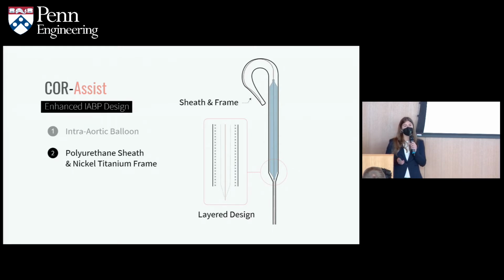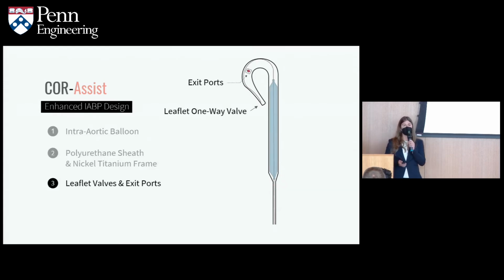The polyurethane sheath reaches into the left ventricle, providing direct support to the ventricle and therefore increasing the flow rate. The nickel titanium frame provides structure for a device and allows for it to expand once pushed out of a catheter due to its memory properties. In order to allow for proper flow in and out of the left ventricle, we included a leaflet one-way valve and exit ports. The one-way valve allows for blood to be pulled from the left ventricle without any flow back in, and the exit ports allow for blood to be pushed out into the aorta.